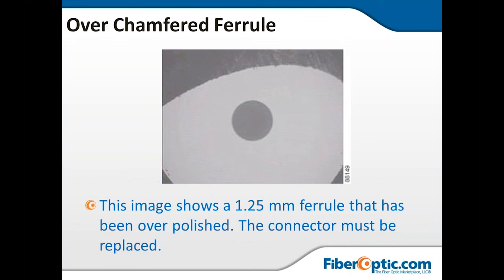This is a 1.25 ferrule, as it says here, and it was overpolished. When it's overpolished, it's probably very pointy and likely fails the IEC spec. The fact that you can see that dark area means it doesn't conform to the specs it needs to meet, and it probably needs to be replaced or repolished.